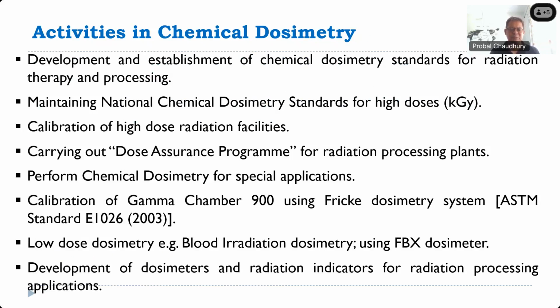Any radiation facility using a high dose radiation field, their dosimeters have to be calibrated. So this particular group gives the calibration facilities. Then they carry out a dose assurance program for radiation processing plants. For example, a particular plant is giving a certain amount of dose, whether they are giving it correctly or not. So assurance programs are carried out to give them confidence that they are doing it the correct way and the correct dose is being delivered.